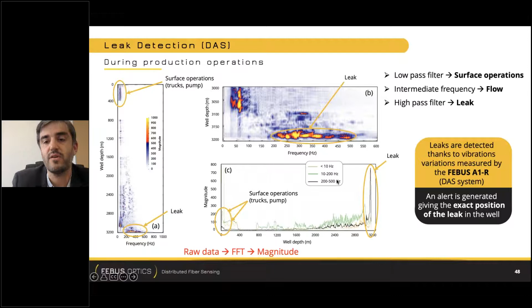Finally, I'll show you a well integrity application measuring strain on the casing. First, if you want to measure strain on the casing, the best way is to attach the fiber to the casing directly. The cable has to be quite particular and should be tight buffered, because otherwise, if the cable is not tight buffered, the optical fiber will slip inside the cable, decreasing the sensitivity.